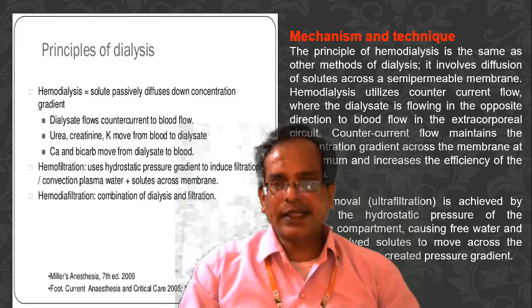The mechanism of dialysis and its techniques. The principle of hemodialysis is the same as the other methods of dialysis. It involves the diffusion of solute across the semi-permeable membrane. Hemodialysis utilizes counter current flow, where the dialysate flows in the opposite direction to the blood flow in the extracorporeal circuit. Counter current flow maintains the concentration gradient across the membrane at the maximum and increases the efficiency of dialysis. Fluid removal or ultrafiltration is achieved by altering the hydrostatic pressure of the dialysate compartment, causing free water and some dissolved solute to move across the membrane along a created pressure gradient.